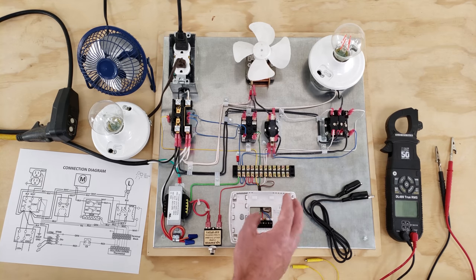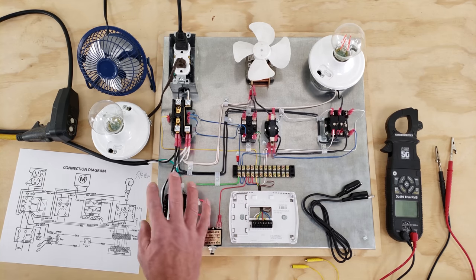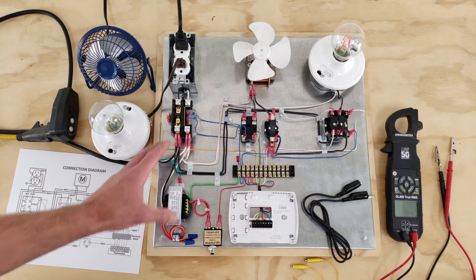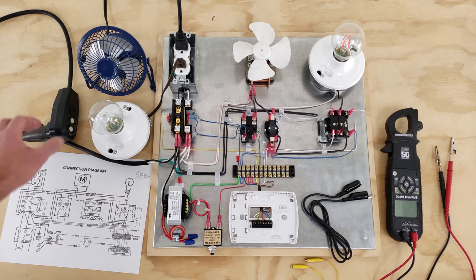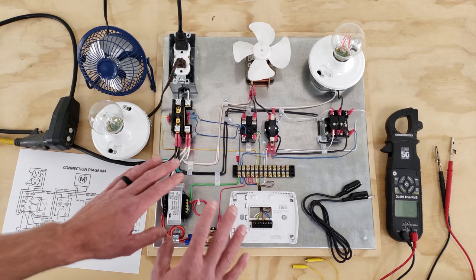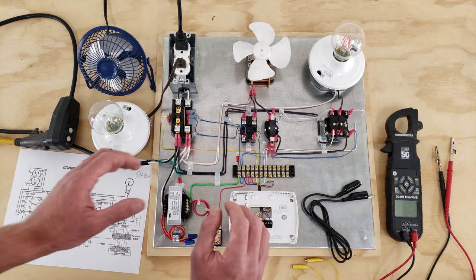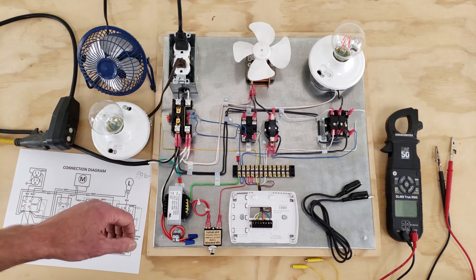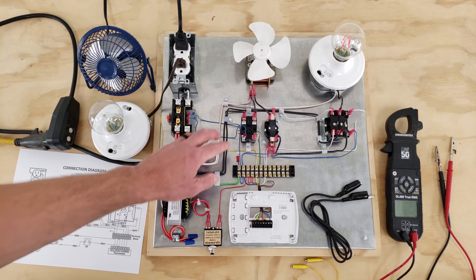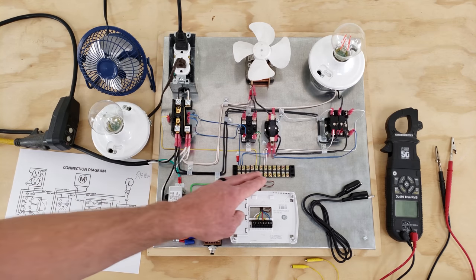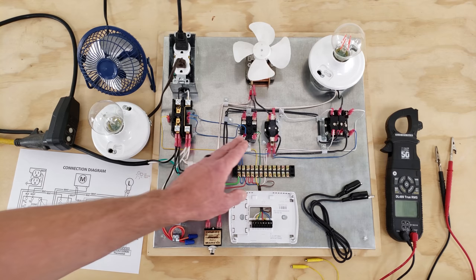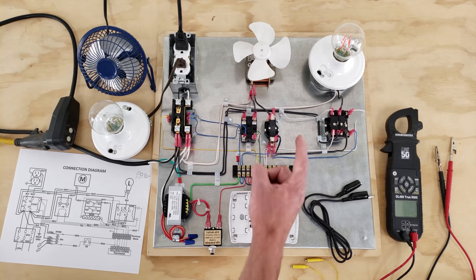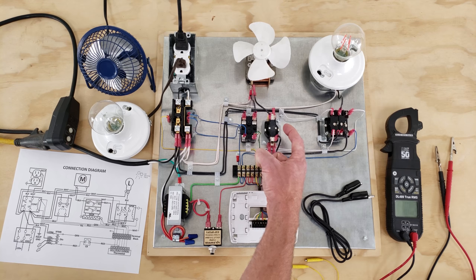And you have the terminal block, so you might mount this, and this, and start wiring them. And we have our power wire into our contactor, maybe put your GFCI in. So you'd start off with those several components first, and then you would move on to your other components. Maybe you would do your high voltage electrical wiring next, or you would do your low voltage electrical wiring to each of these relays. Remember that this sometimes is called a sequencer relay, but it's really not.